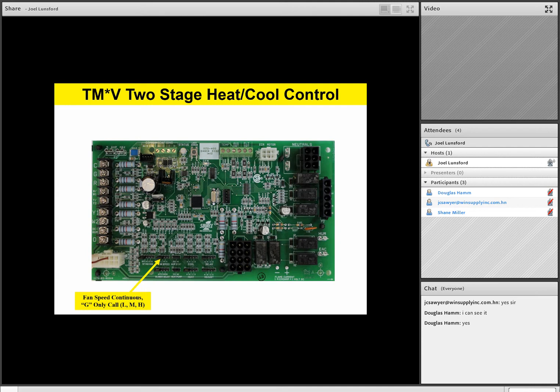Okay, well, down below, your fan speed selection is going to be your blower delay. That blower delay is your heating off delay. And again, that's field selectable from 60, 90, 120, or 180 seconds. Typically from the factory, we set that up on our furnaces for about 120 seconds. 90 to 120 seconds will be where the jumper is from the factory. And so that is field selectable for our heating off delay. That's our heating off delay: how long the fan will run after the call for heat goes away. You can have a field selectable jumper, 60, 90, 120, or 180 seconds.